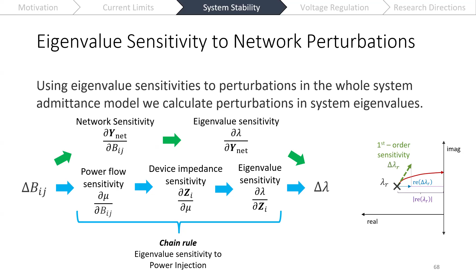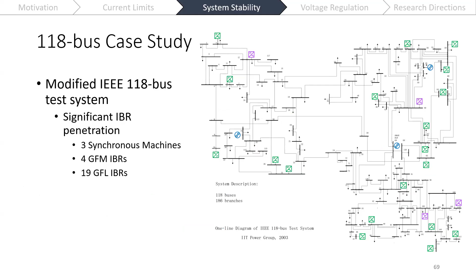This is work that we just recently submitted to the Transactions on Power Systems. In this modified system, we have significant IBR penetration. We have 3 synchronous machines throughout the system, 4 grid forming inverters, and then 19 grid following inverters. We go ahead and calculate the line admittance sensitivities for an increase in line admittance, so if you somehow could switch another line on in that case, or a decrease in line admittance, giving an idea of how sensitive our system is if we have an outage of that line.